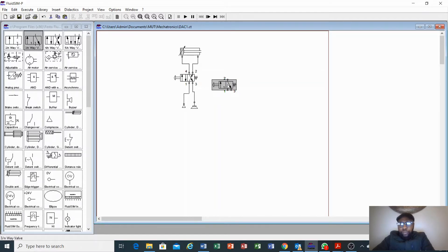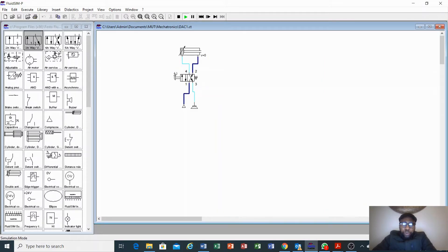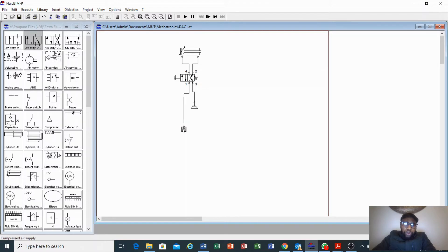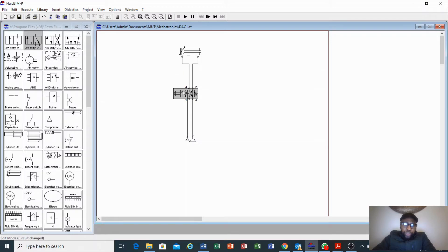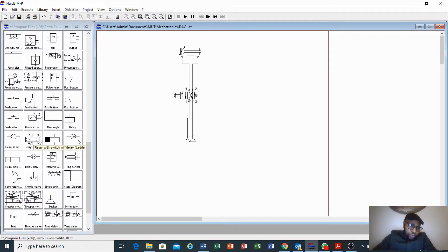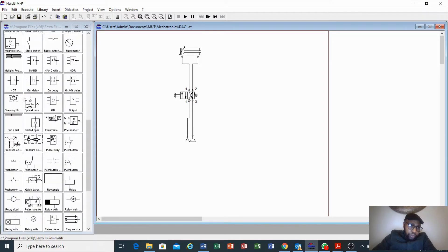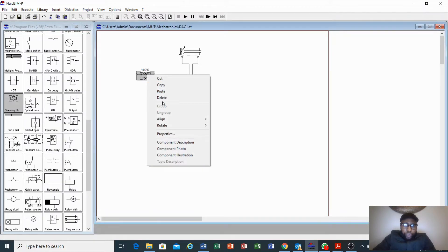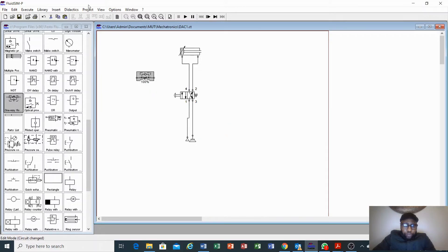This is how we control our double-acting cylinder — basically using a 4x2 with a push button. Now I want us to observe something: if we press play and push our button, our cylinder extends very fast. The question is how to control that. We have what you call a one-way flow control valve that you can use when extending to slow the flow, so that we are able to see the extension with our eyes. You search for one-way flow control valve.